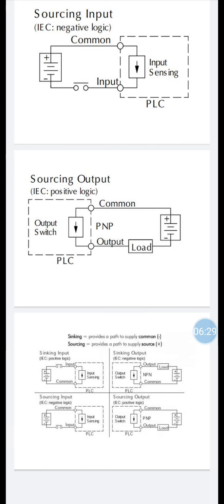The common terminal is the terminal which will serve as the common return path for all input output points. Sink source input output circuits combine both sinking and sourcing capabilities. The meaning of this is that the input output circuit in the PLC will allow the current to flow in either direction as shown in the figures.